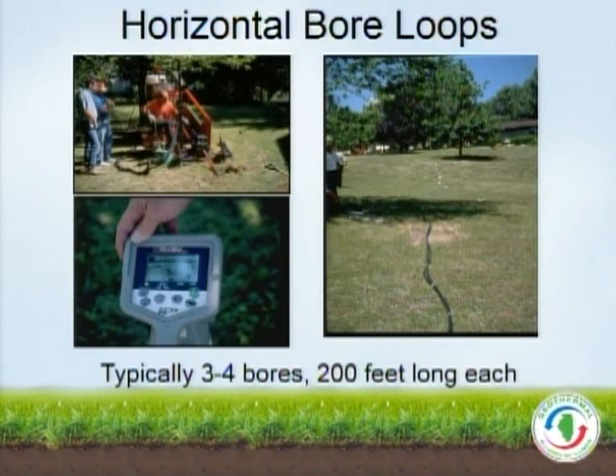This is getting very popular, where you see directional boring machines, the kind used for installing fiber optics and things like that, that you'll see around town. They're also now used for installing geothermal loop fields, and they're getting very, very common. The handy part is, for a contractor, if they invest in a boring machine like that one, which is typically a $300,000 or $400,000 machine, they have to keep it busy.